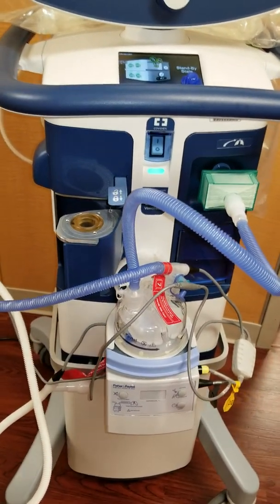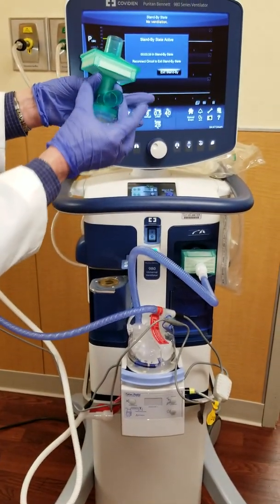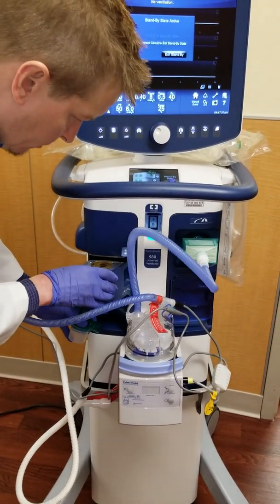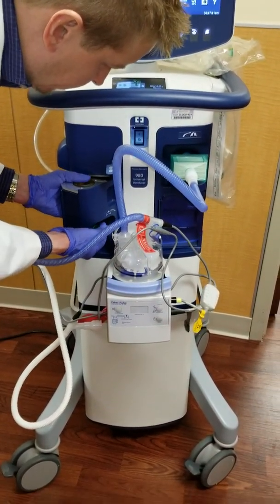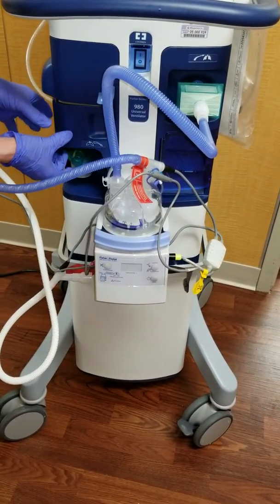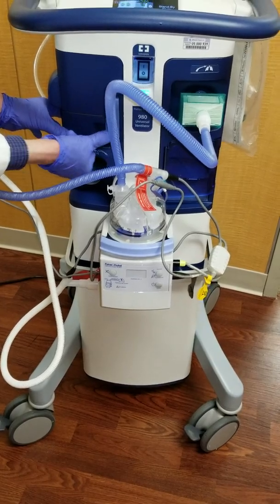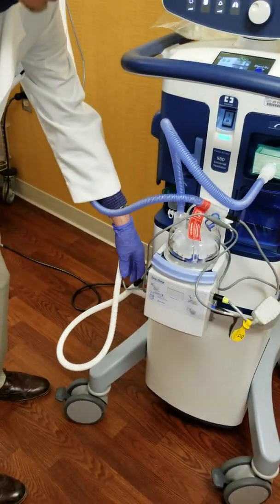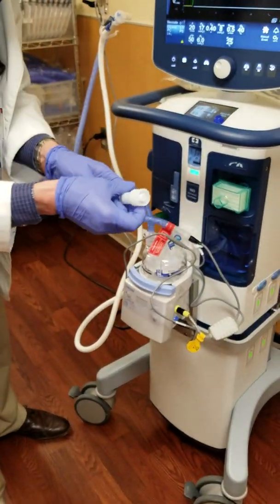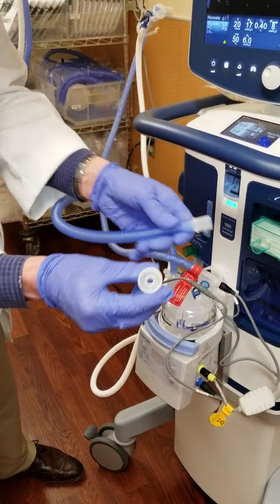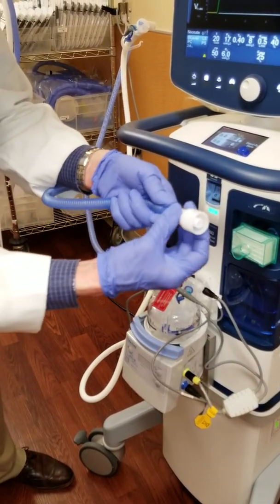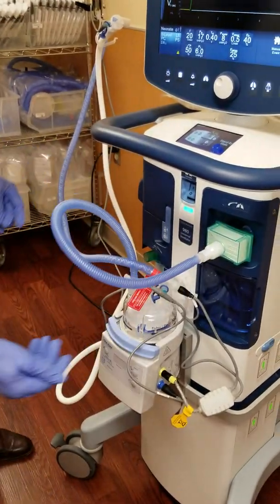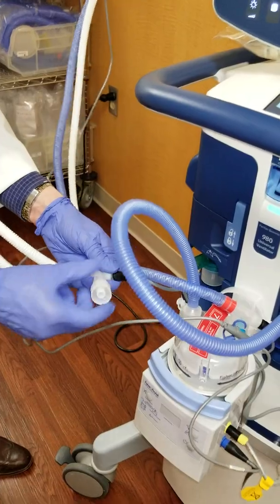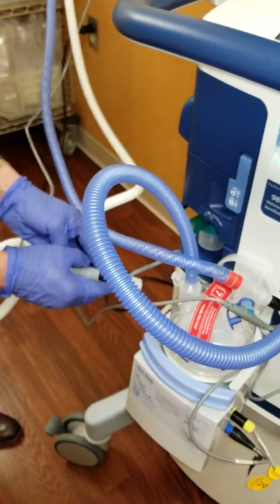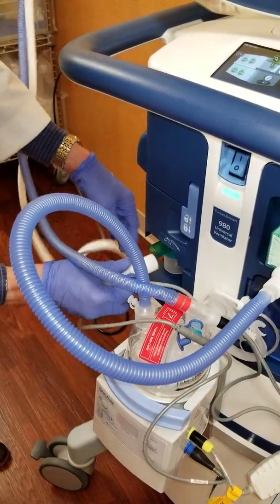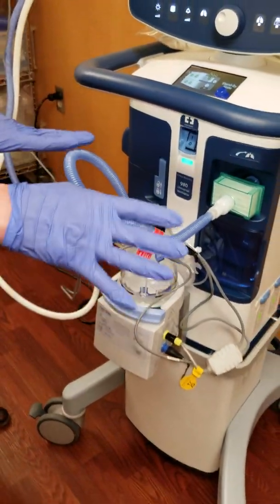Okay? And because it's a special neonatal filter, which just slides up from the bottom. Just fit it in there to where it's nice and snug. Door closes and you snap it shut. Okay? Now with our circuits, we had to use some adapters that came with them, because this would not fly. So use an adapter, okay, on the inspiratory limb and the expiratory limb. So you got to change the filter, change the door, add a couple adapters, and your circuit's ready to go.